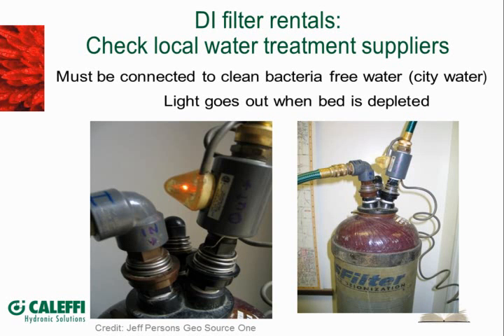Oftentimes with the antifreeze suppliers, they will pre-mix and bring it to the site in trucks for commercial projects. What we typically do is we keep a DI column at our offices, and a service comes around and they'll replace that every month. They'll exchange it for a new media bed. But we'll run chlorinated city water through the DI column. The water coming out of the column is the same quality as you would have with distilled water. And a neon lamp on that column tells you whether your discharge water is of good quality or if it's containing minerals and the column is being depleted and it's time to get an exchange. It makes it very easy because we can fill a 500-gallon tank in one of our trucks and cart that to a job site and then pump that down into the systems to fill them.